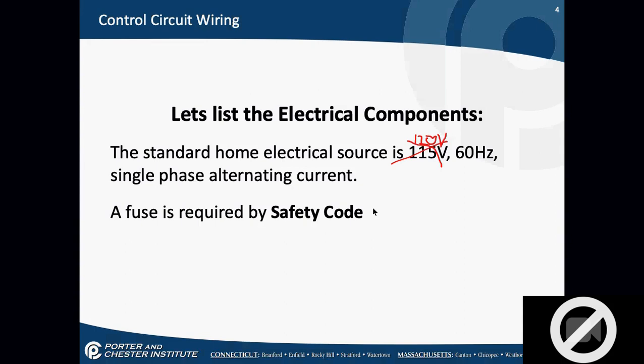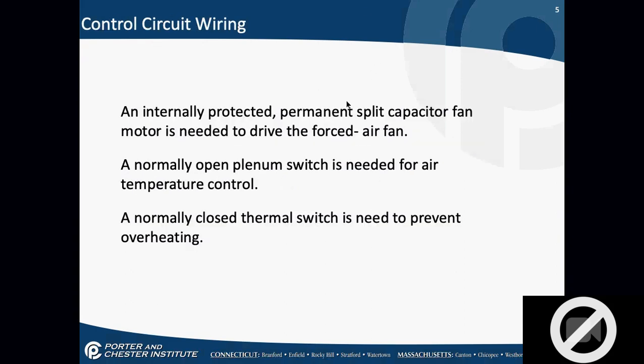So we have to have the electrical components. Our source, a fuse or breaker, and we have to have an internally protected fan motor, which basically means it has an internal motor protection device. We have to drive the forced air fan. We have to push the air around the house. This is known as our blower motor as well. Okay, forced air fan motor. PSC, we talked about it yesterday, has a capacitor inside of it. We have to have a normally open temperature sensitive switch for temperature control.